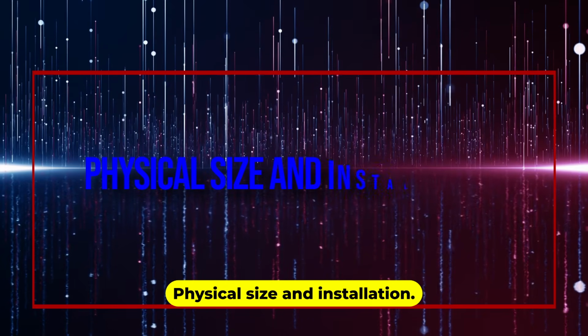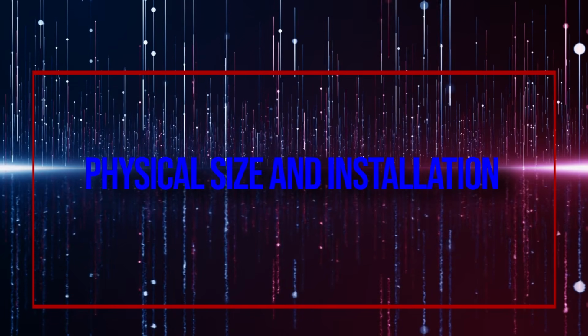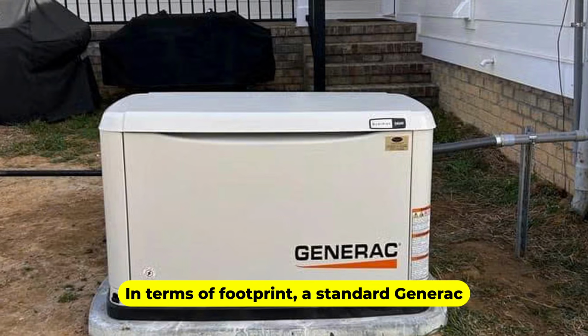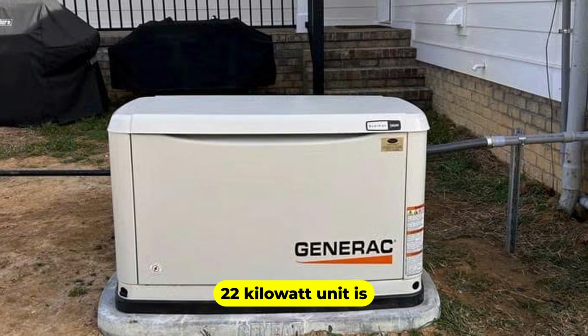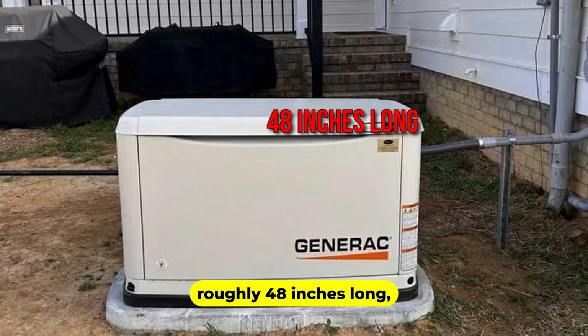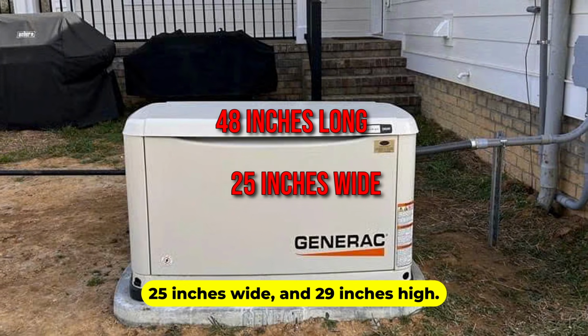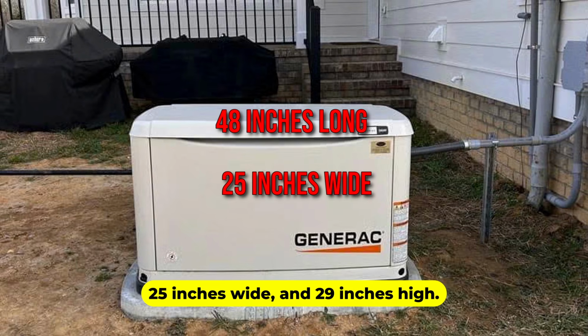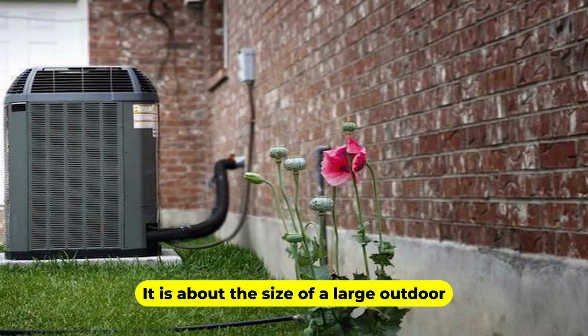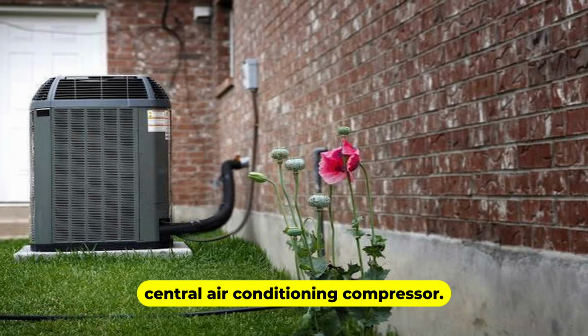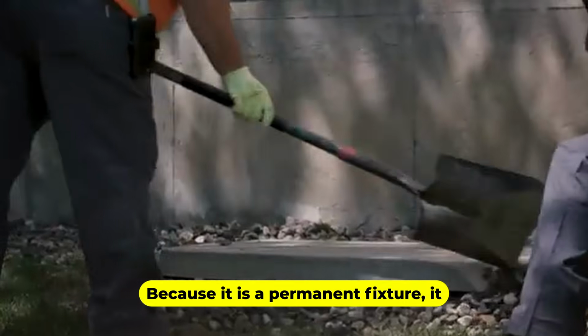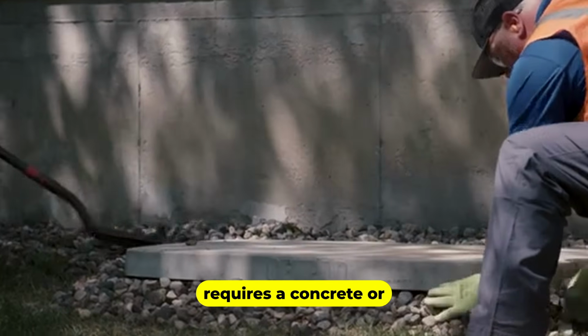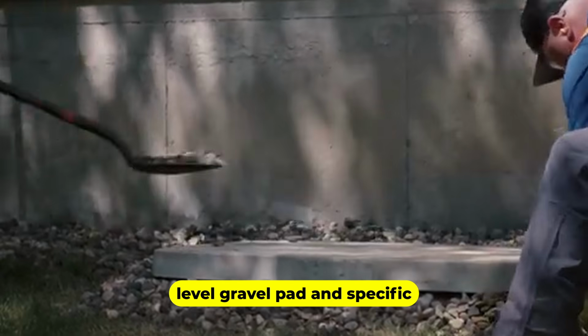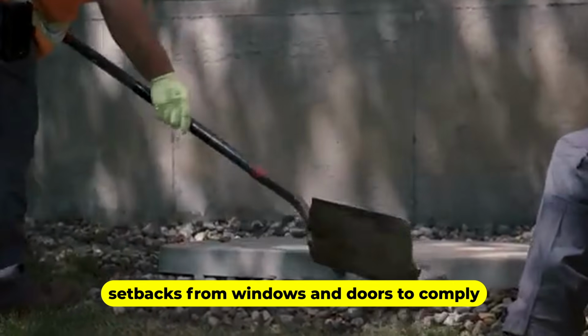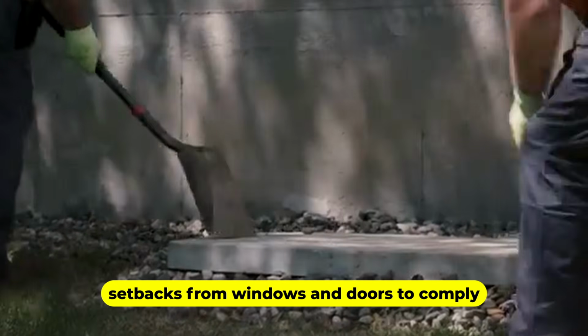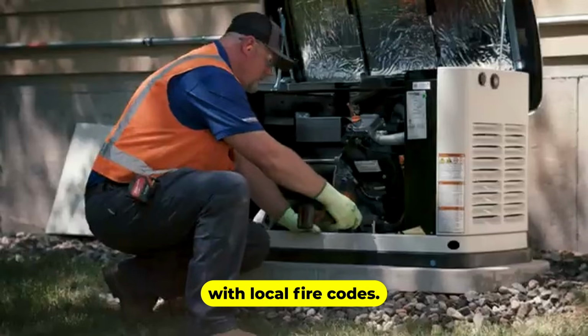Physical size and installation. In terms of footprint, a standard Generac 22 kilowatt unit is roughly 48 inches long, 25 inches wide, and 29 inches high. It is about the size of a large outdoor central air conditioning compressor. Because it is a permanent fixture, it requires a concrete or level gravel pad and specific setbacks from windows and doors to comply with local fire codes.